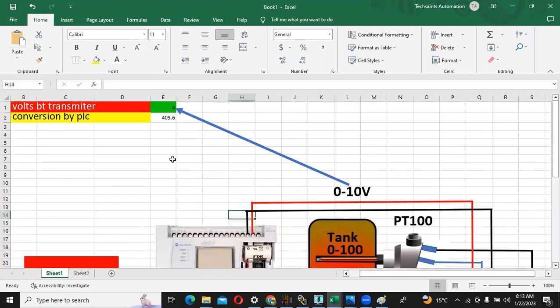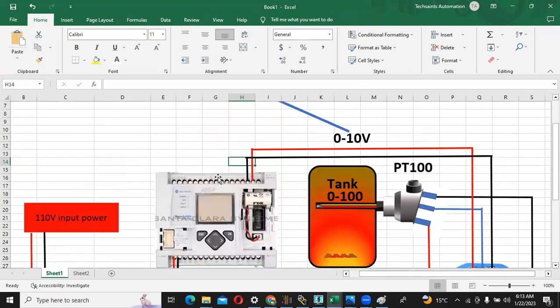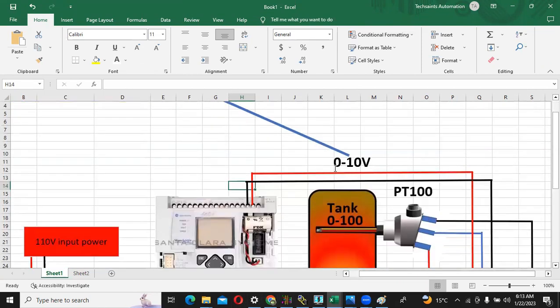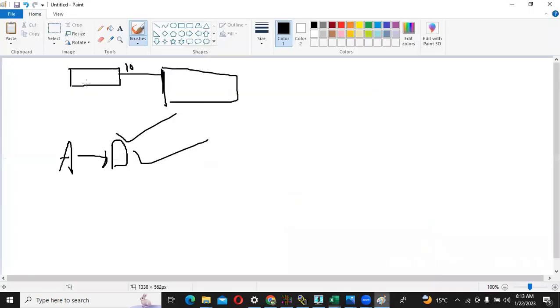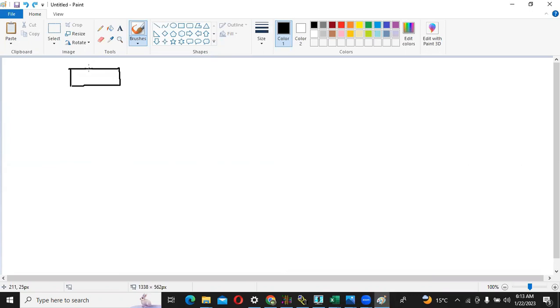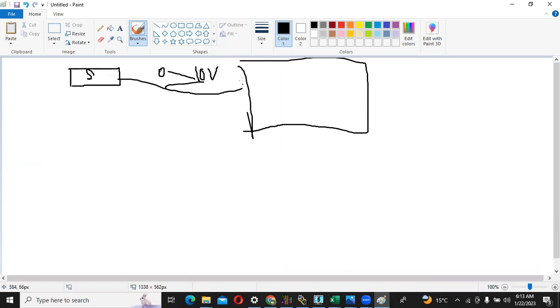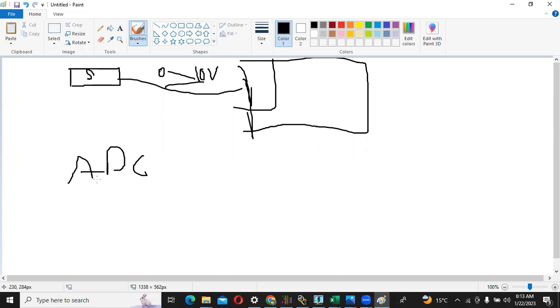When we move forward, I am going to show you what is behind all of this. Actually this 0 to 10 volt is not considered by PLC directly. Suppose this is my sensor and it is converting the temperature into 0 to 10 volt, and this input voltage is coming to the PLC. The PLC processor did not use this one directly. Inside of the PLC, there is an analog to digital converter ADC. This analog to digital converter converts analog values into digital values.